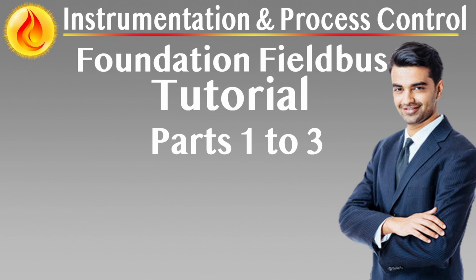All Fieldbus-ready instruments must be registered with the FieldComm Group and include a device description (DD) and capability file (CF). These files ensure consistent behavior across host systems, allow accurate graphical representation of device parameters, and support full engineering and diagnostics integration. Devices lacking DD-CF registration are not permitted for installation in the Fieldbus network.